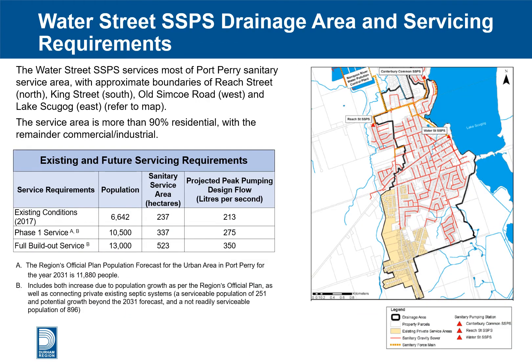The Water Street SSPS services most of the Port Perry Sanitary Service Area, with approximate boundaries of Reach Street to the north, King Street to the south, Old Simcoe Road to the west, and Lake Scugog to the east, as shown in the map. The service area is more than 90% residential, with the remainder being commercial and industrial. Currently the pumping station services a population of 6,642 people, with a sanitary service area of 237 hectares and a projected peak design flow of 213 litres per second.